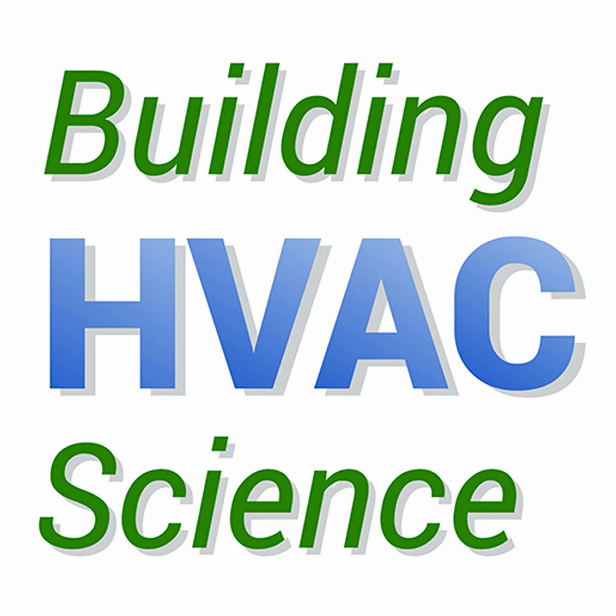And the third question is dew point. What dew points can you get down to? We can actually get down to a 35-degree dew point. 42 is a basic, straightforward process. For 35, we just do a little bit more checking, since you're pushing things. But we're very able to do that, which allows us to cover not just core DOAS applications like a hotel or a school, where you're treating air and getting it down to a 50 to 55-degree dew point, but also grocery stores and industrial or food processing applications, where you're pushing down to that 35-degree dew point because you have to get to drier conditions.